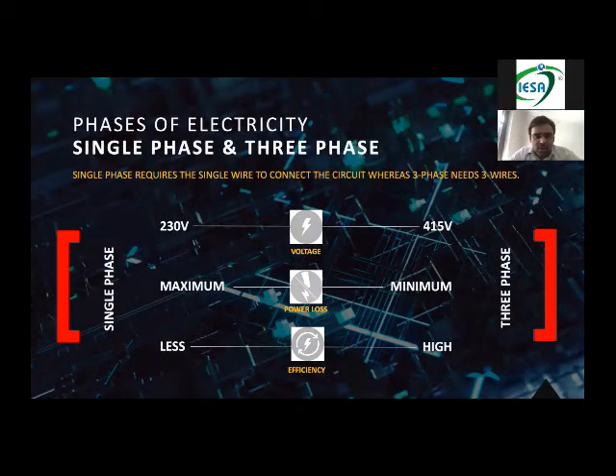So basically, it depends on the power requirement. All the gensets which are being produced, everything is 3 phase. You see all the gensets, they have 4 links: black, red, yellow and blue. So automatically you are taking 3 phase power and then you can convert it into single phase. If you have single phase requirements, that can be done on site, but everything is 3 phase only. Then after that it gets converted into single phase.